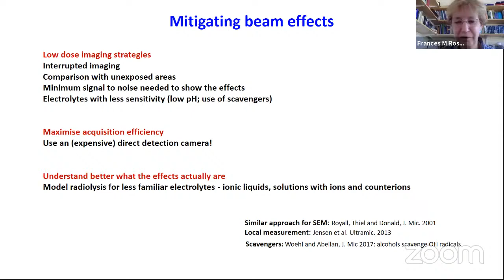effects. But I've already referred to the fact that the microscope is going to be changing the sample as you do the imaging. And so that makes us think about what really limits the resolution of the images in a liquid cell experiment. For very thin samples, or for samples where you don't care how many electrons you use to make the image, the resolution is limited by the performance of the microscope. But it's much more typical that the resolution is dose limited. In other words, you cannot shine enough electrons on it to see your object over the noise, because the sample is too sensitive to the electron beam to be worth imaging after you've illuminated it with so many electrons.